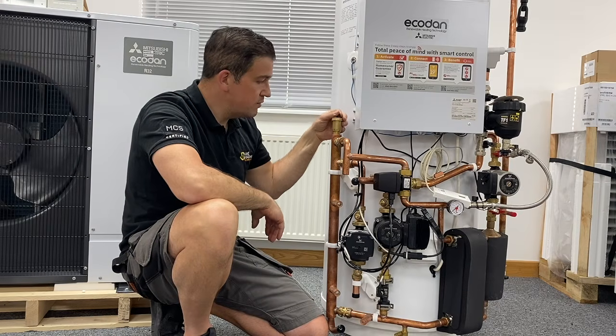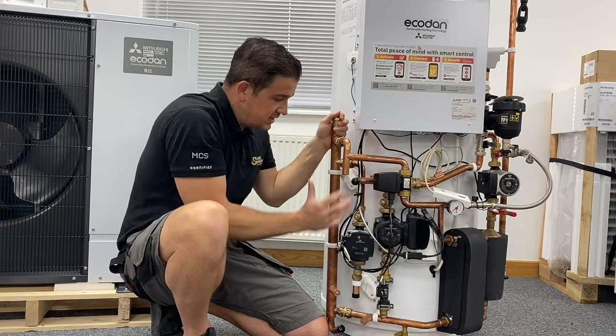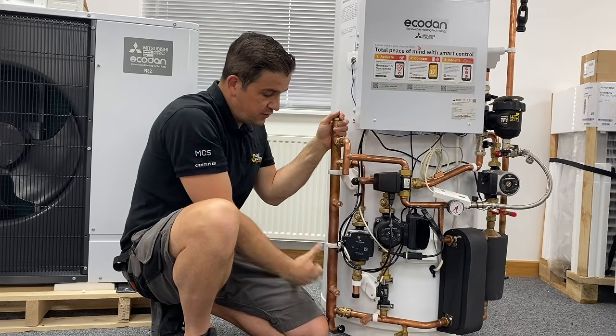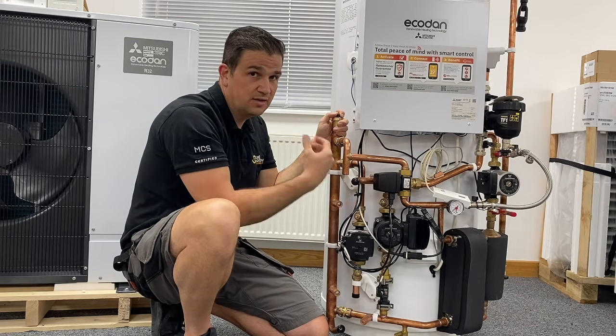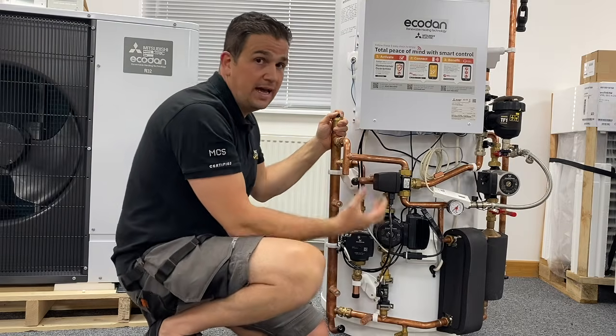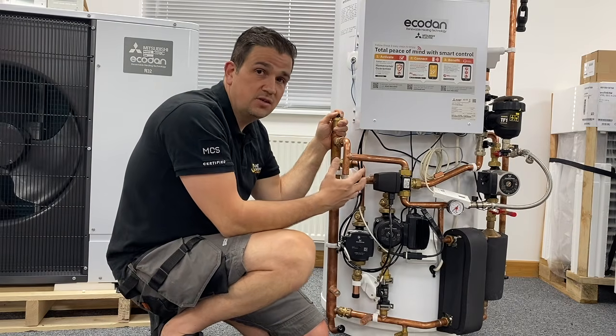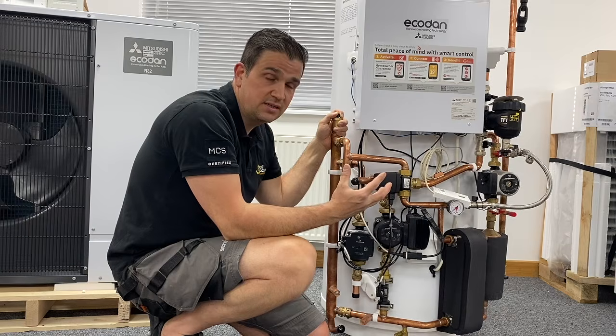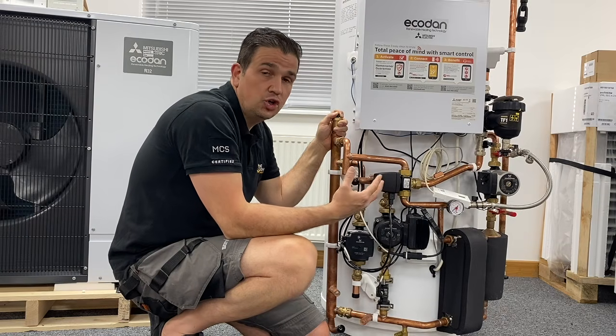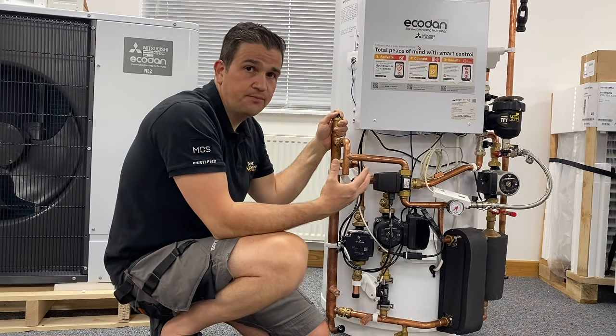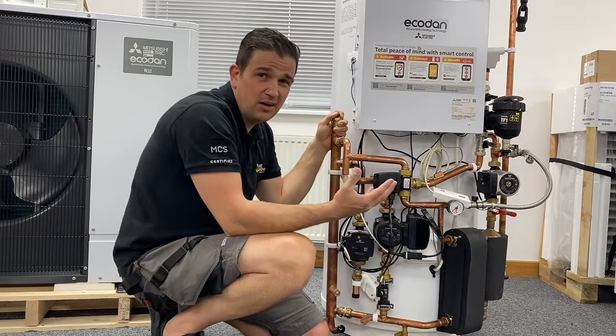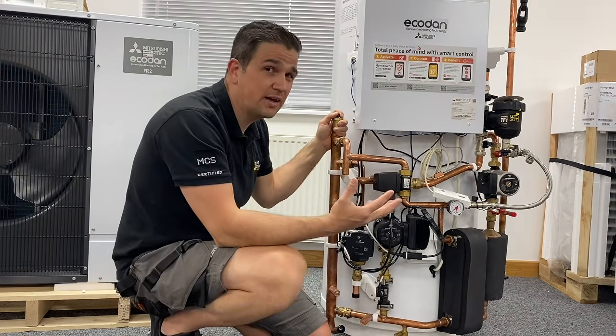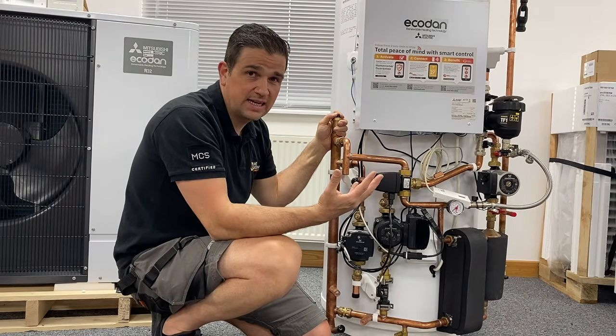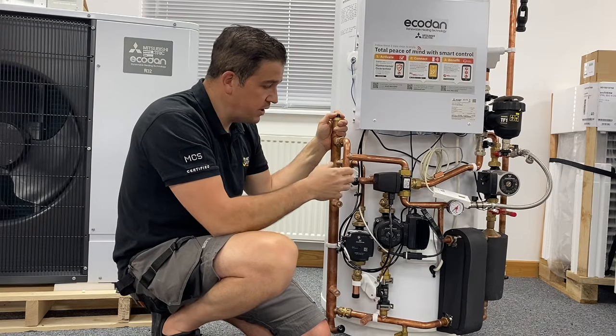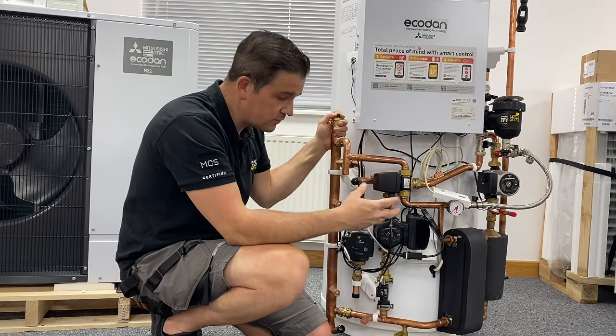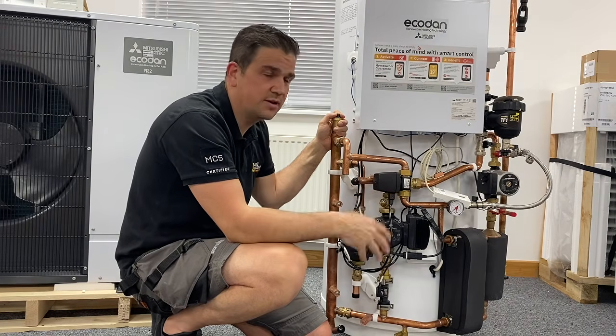And the capacity of what this enables us to do on the hot water side is one of the reasons why we are able to use this system without necessarily putting in a buffer tank, should the system allow for it. Now, if it's a fairly large heating system, we would recommend putting a buffer tank in, but I think that just comes down to what we look at and how we would design the system.